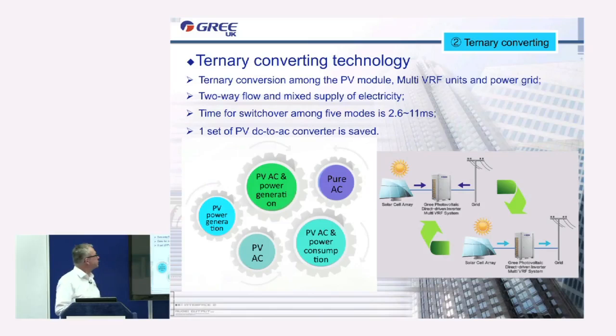The second one I mentioned was ternary converting technology. This is where we have the three main components, which is the PV cells, the VRF itself and the power grid. The important point to mention is that it's all built in. Now you don't need any additional components to control this power flow. And as I mentioned before, the switchover time is very fast, and therefore we can reduce also one set of DC to AC converters.